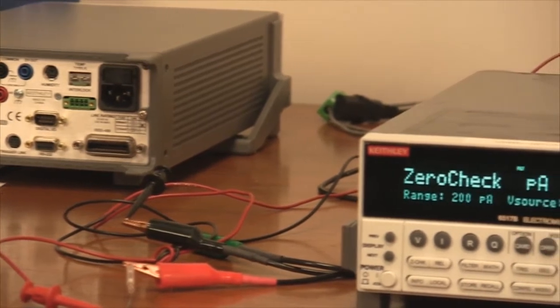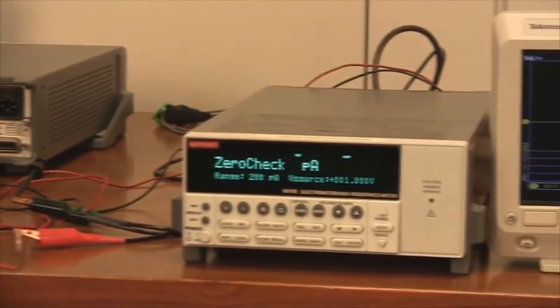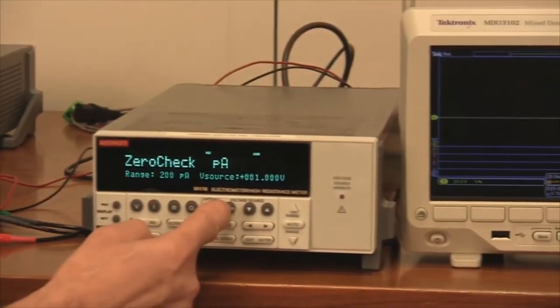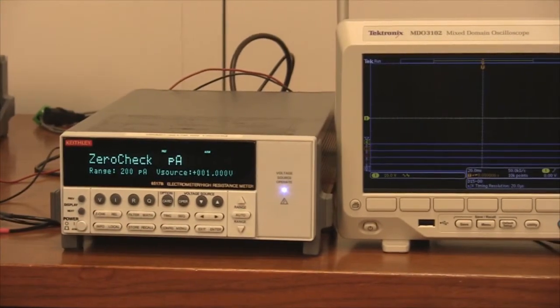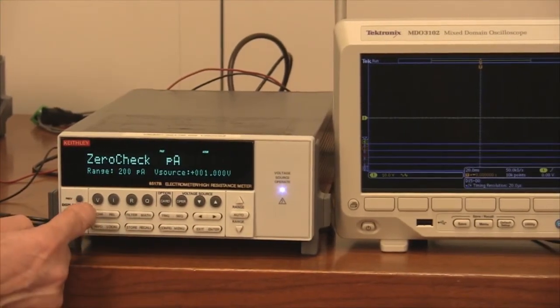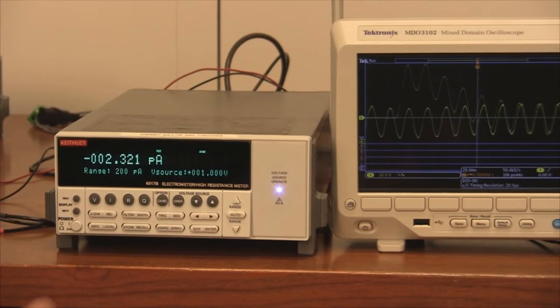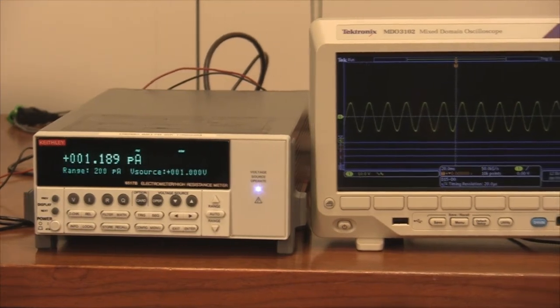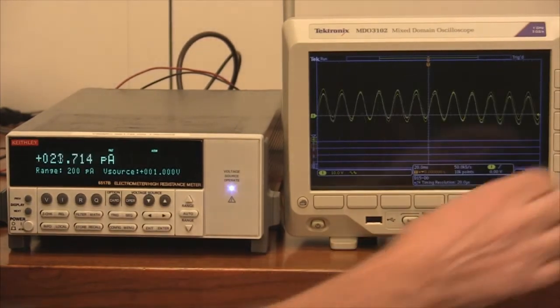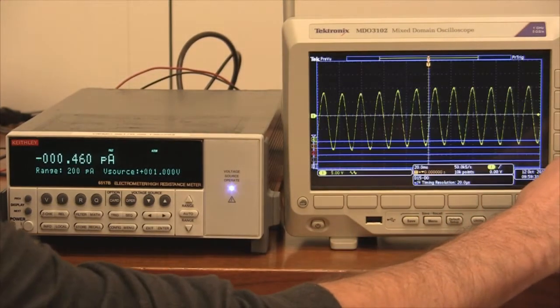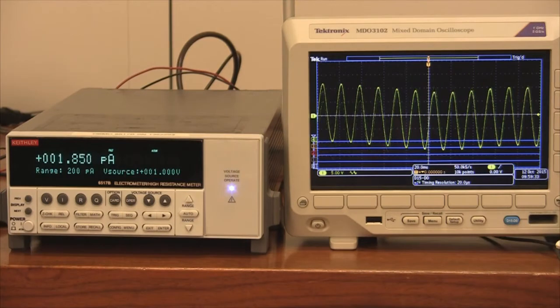Okay, now let's get back to the front panel. All we have to do is hit operate and release zero check. Notice it's all over the place. If you can pan over to the oscilloscope, you can see that's the preamp out, fairly noisy.